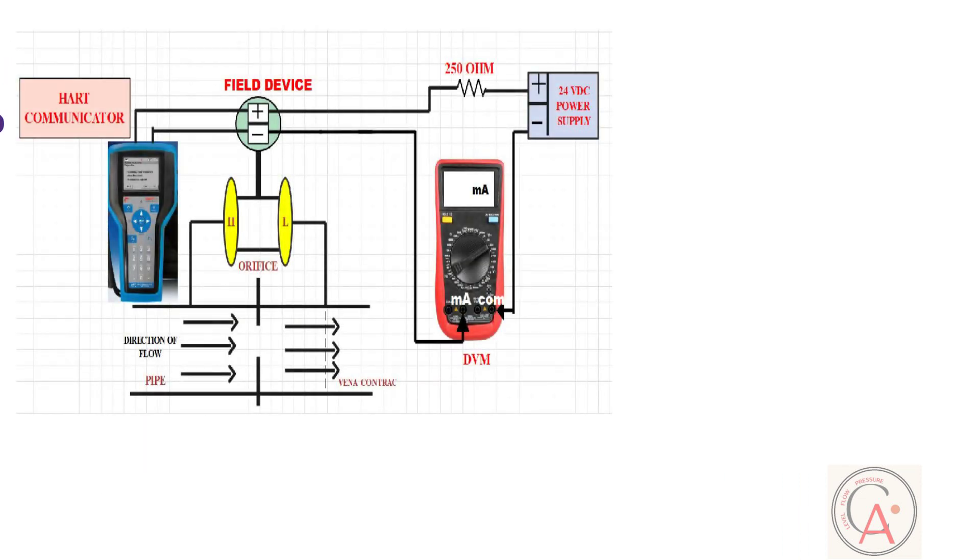As you can see, to perform digital to analog trim, connect ampere meter in series with transmitter, and also connect HART communicator to positive and negative terminals of transmitter. Once connection is done, turn on HART communicator and start HART application.